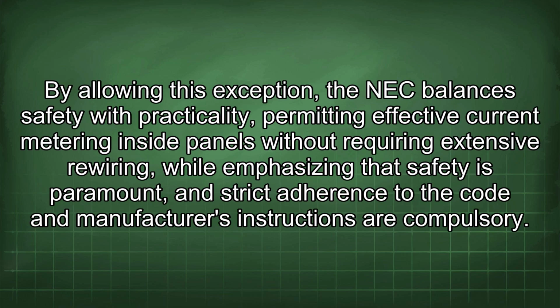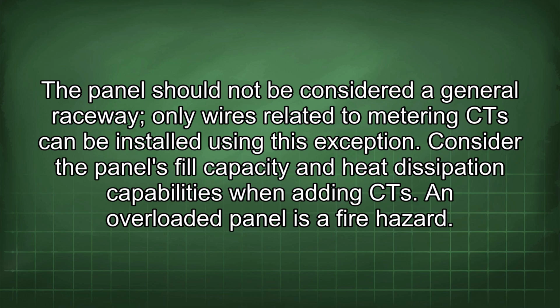methods. By allowing this exception, the NEC balances safety with practicality, permitting effective current metering inside panels without requiring extensive rewiring, while emphasizing that safety is paramount and strict adherence to the code and manufacturer's instructions are compulsory. The panel should not be considered a general raceway. Only wires related to metering CT can be installed using this exception. Consider the panel's fill capacity and heat dissipation capabilities when adding CT. An overloaded panel is a fire hazard.